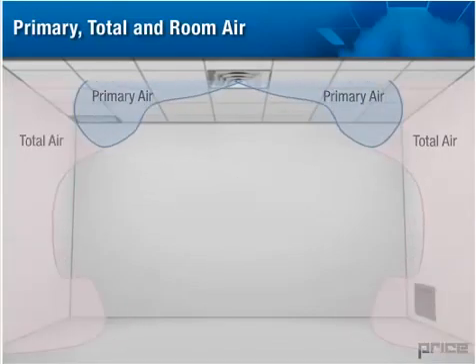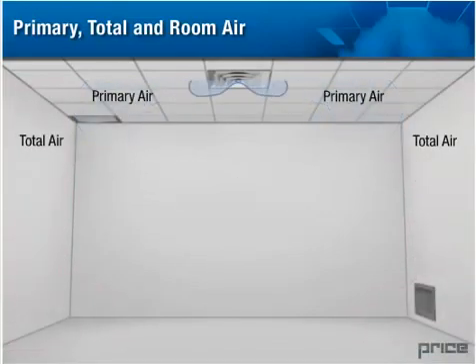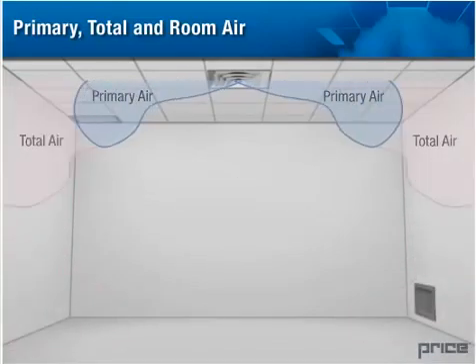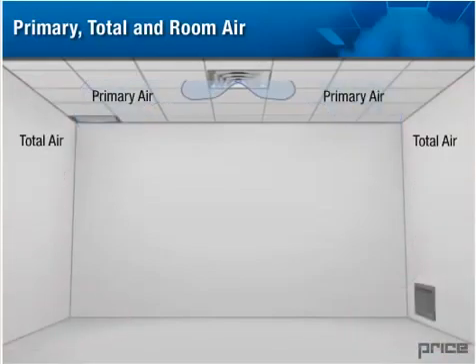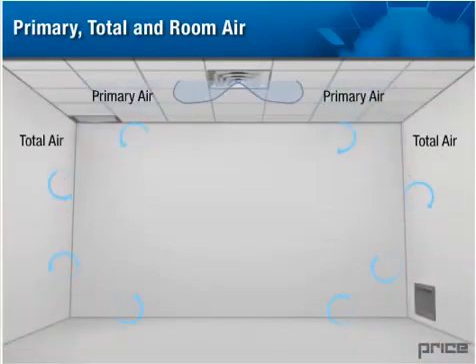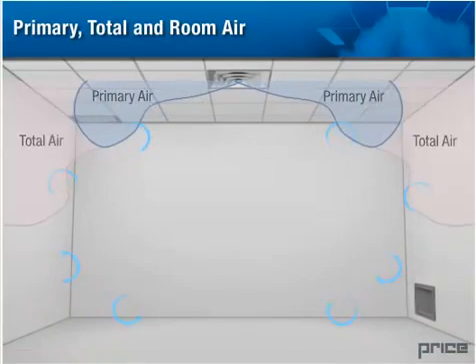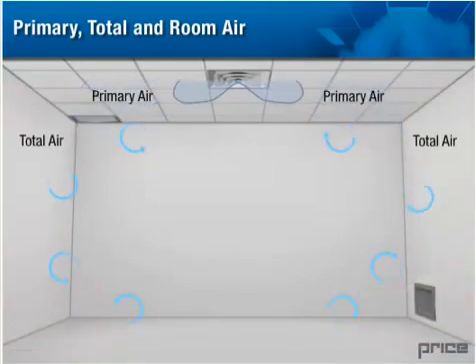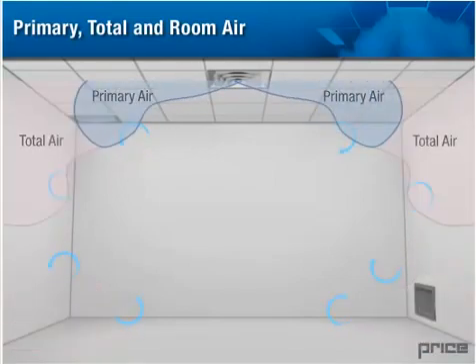Total air is the total volume of air in the room which is under the influence of the primary air stream. This is the primary air and the induced room air moving out from the air outlet. The total air is usually considered to be the volume of air within an envelope of fifty feet per minute or higher air velocity.